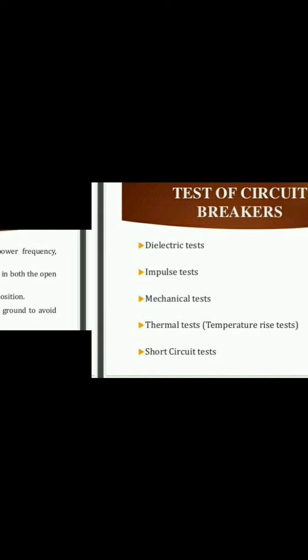Let's start with the first type of test, called the dielectric test. The name itself indicates the meaning of the dielectric test. In this test, we are substituting some dielectric media for the arc interruption quality. This type of test is called a dielectric test. This test consists of the over voltage withstand test of power frequency, lightning and switching impulse voltage, tested for internal and external insulation with the circuit breaker in both the open and closed position.